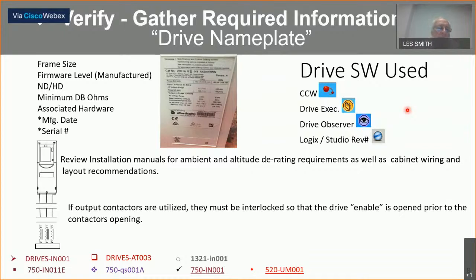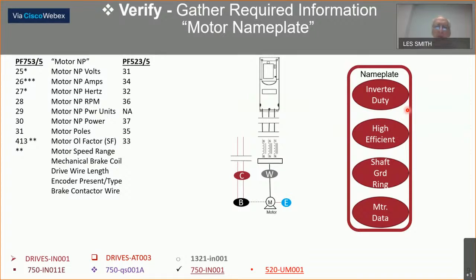Note here, review the installation manuals for ambient temperatures and altitudes for derating. That's very important. And here they call out output contactors, the next one down. That's not as popular today as it was in the older drives, but they make note of it a lot, so I kept it in there. And in the same manual, I'm asking where you get the information off the nameplate, be aware. I realize you may have dozens or hundreds of motors out there, but understand when I come out, I usually have just one motor to look at. So I hone in on that so I can get a better understanding of that particular application.